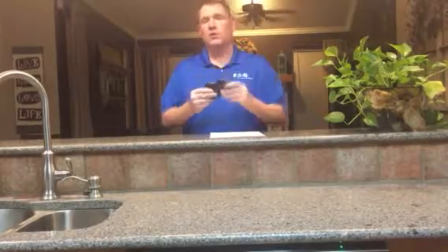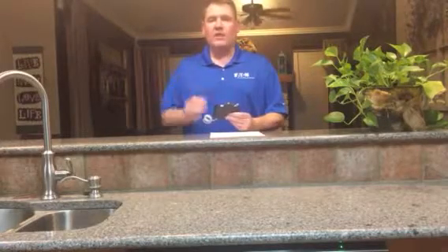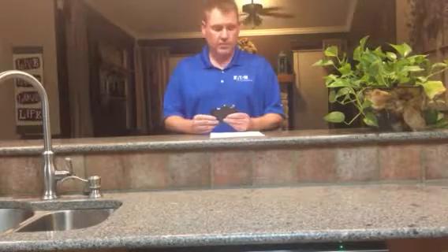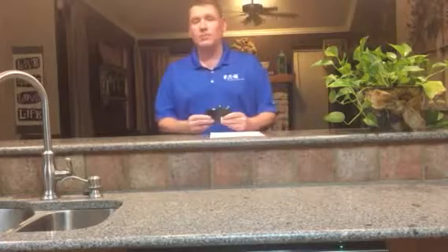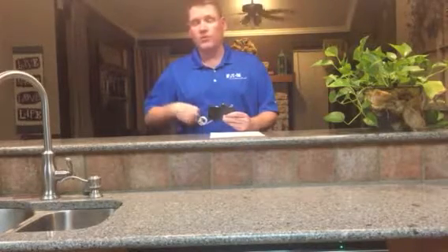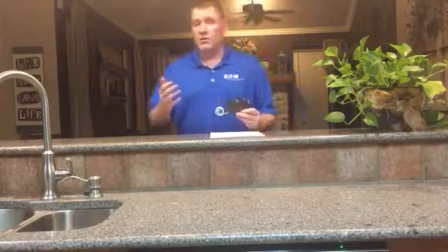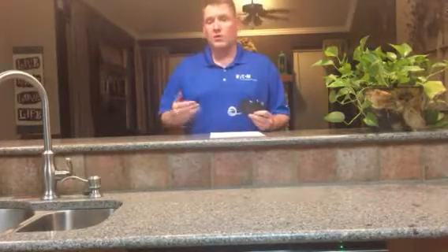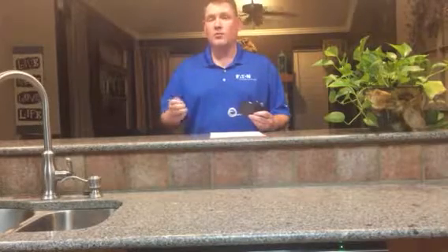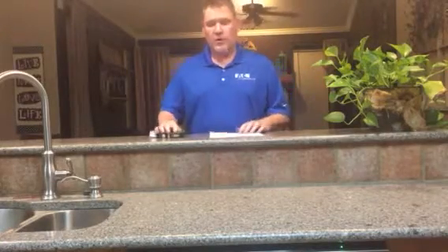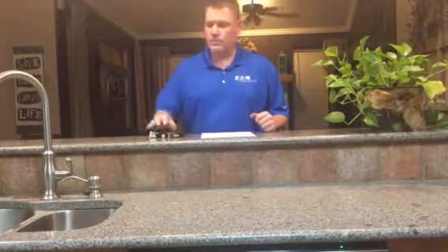So with the breaker closed, say you've got a hair dryer and a fan on the same circuit. I can tell you with experience that overloads that circuit, puts a burden on it. That being said, this is a 15 amp breaker. You're probably going to pull anywhere from 20 to 25 on that circuit. Once this breaker senses that, it is going to trip and open that circuit. That's going to tell you, uh-oh, I don't have power, something's wrong. So what that basically tells you is you need to unplug one of those devices because you're putting too much burden on that circuit. With all that being said, the protection device is called a trip unit.